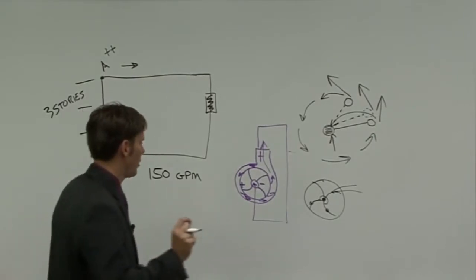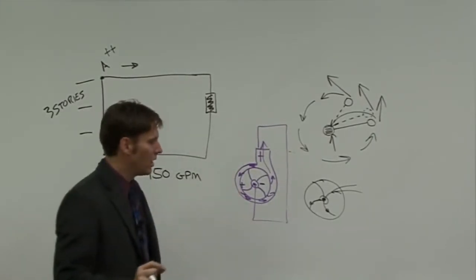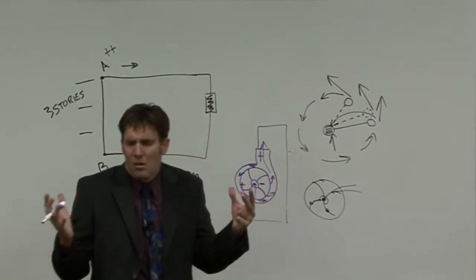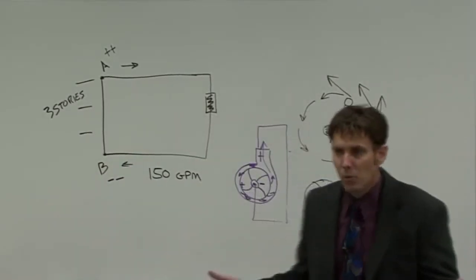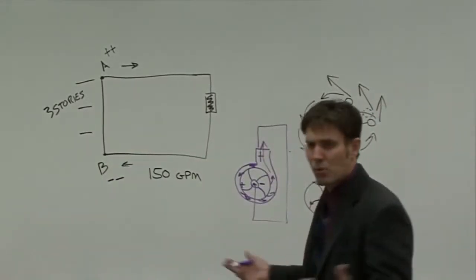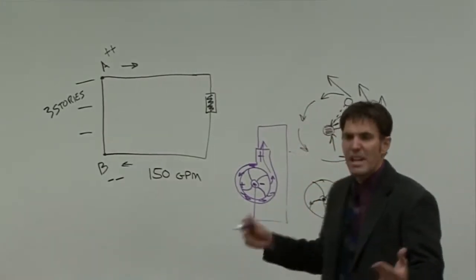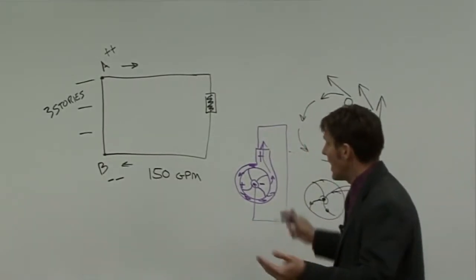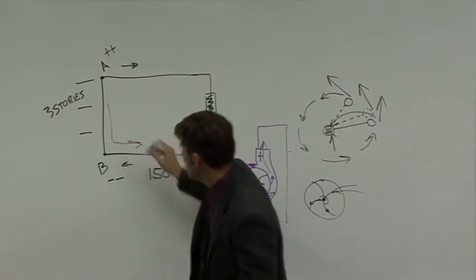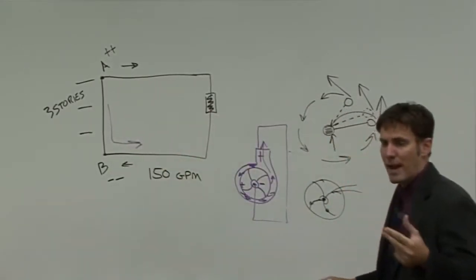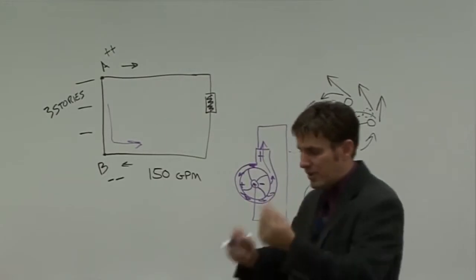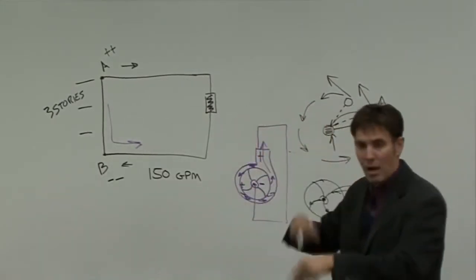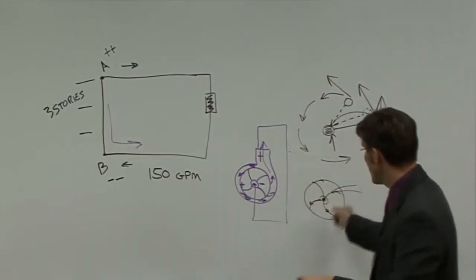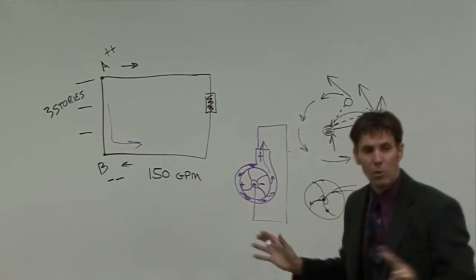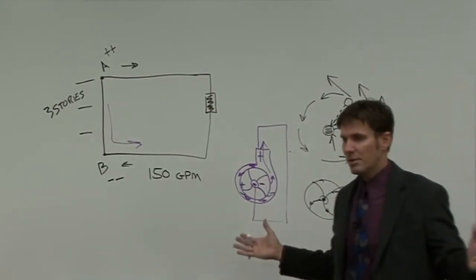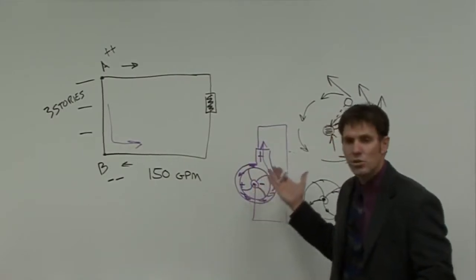That motion creates that differential pressure because of this. Now, I get asked all the time, Joe, my pump is wired backwards. My pump is rotating backwards. My motor's spinning backwards. Am I going to now move flow in this direction? If my pump is wired backwards, because I'm a three-phase motor, and so we simply cross the lines and now my motor's rotating backwards, my pump is spinning backwards, does that mean I'll now flow in the reverse direction? No, because it all comes back to centrifugal motion.